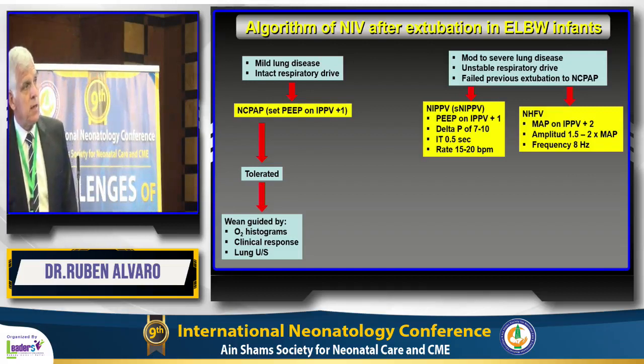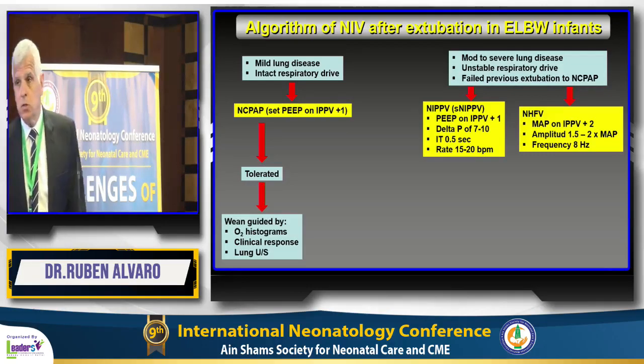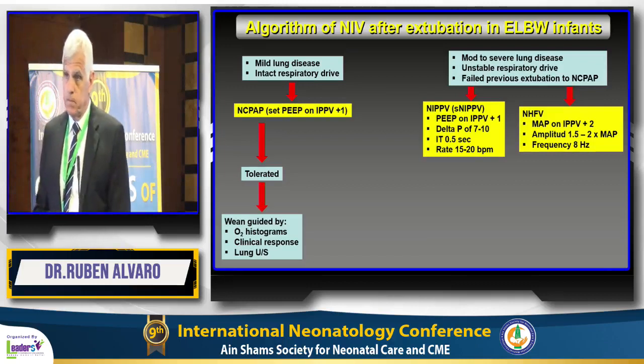If you're going to use nasal high frequency, we recommend a mean pressure about 2 centimeters of water higher than the CPAP used when intubated. The amplitude should be 1.5 to 2 times the mean pressure, and the frequency usually doesn't need to exceed 8 hertz.